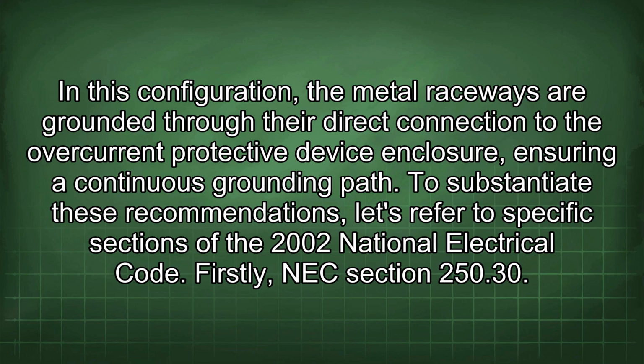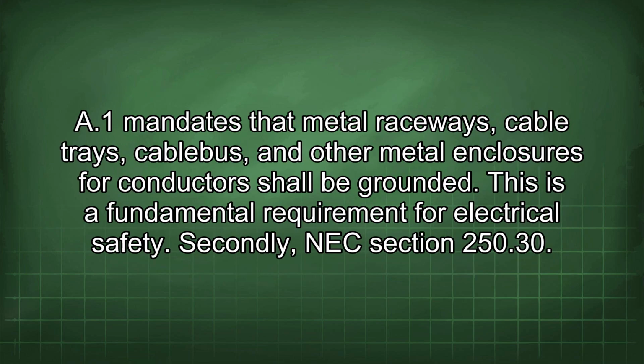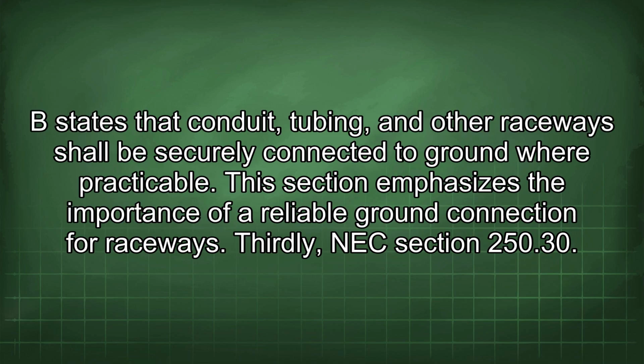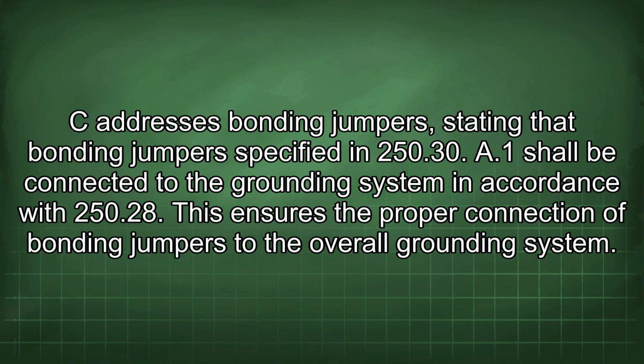Firstly, NEC Section 250.30(A)(1) mandates that metal raceways, cable trays, cable bus, and other metal enclosures for conductors shall be grounded. This is a fundamental requirement for electrical safety. Secondly, NEC Section 250.30(B) states that conduit, tubing, and other raceways shall be securely connected to ground where practicable. This section emphasizes the importance of a reliable ground connection for raceways. Thirdly, NEC Section 250.30(C) addresses bonding jumpers, stating that bonding jumpers specified in 250.30(A)(1) shall be connected to the grounding system in accordance with 250.28. This ensures the proper connection of bonding jumpers to the overall grounding system.